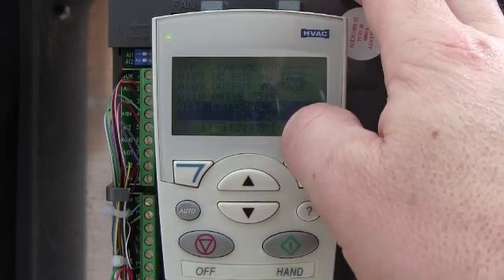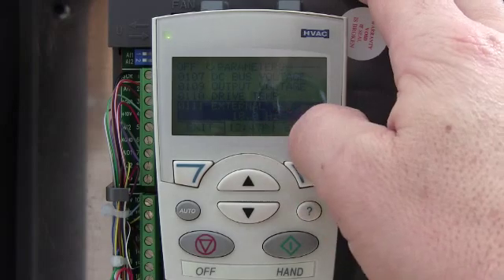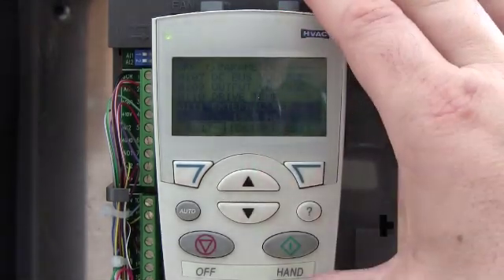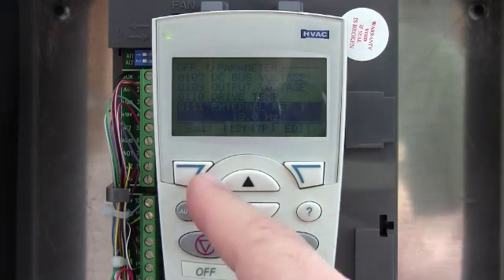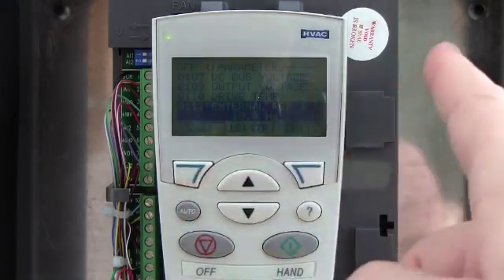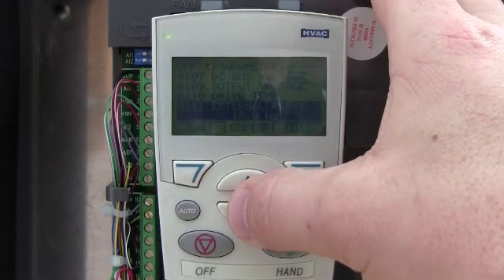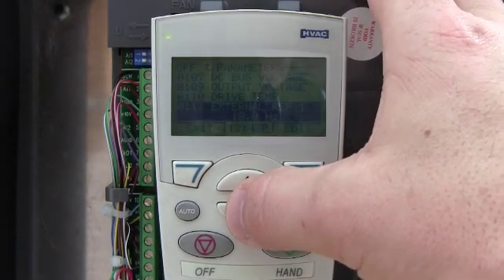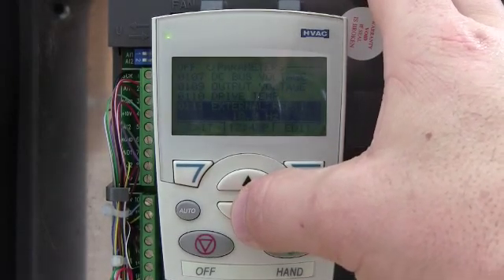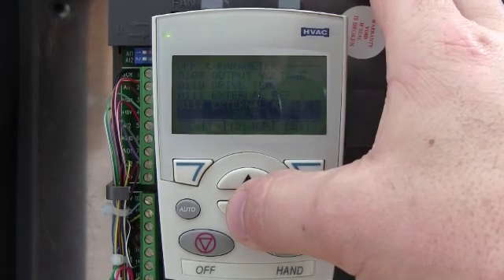External reference one. The reference one, reference two, external one, external two can be very confusing. The nice thing they did on the ABB is external one goes to reference one, external two goes to reference two, nine times out of ten — so it kind of streamlines it a little bit. On the older series drives, you could have that flip-flopped, and it could drive you a little crazy.